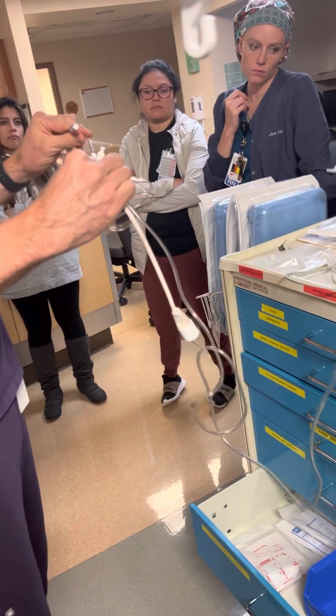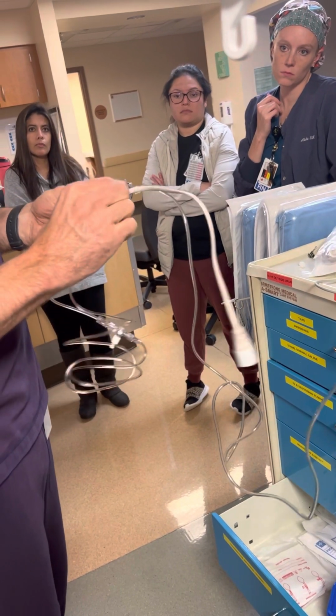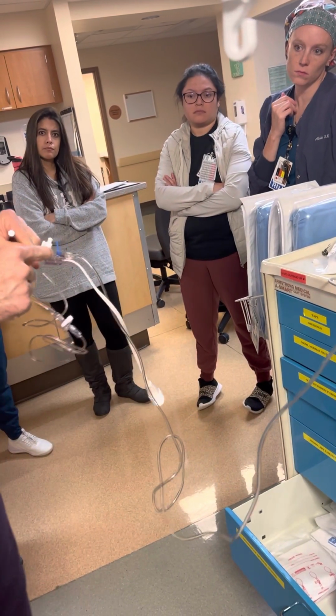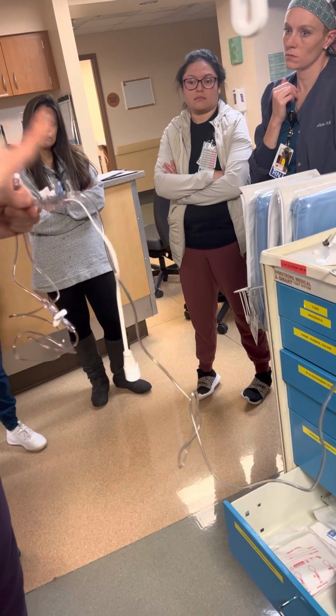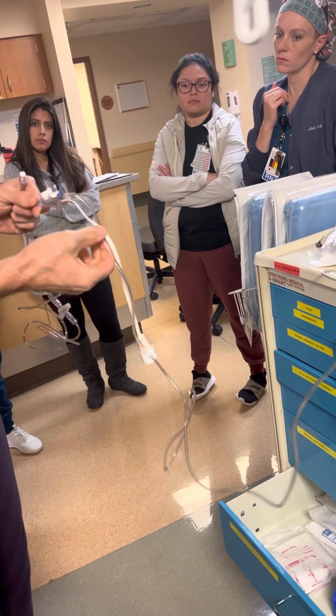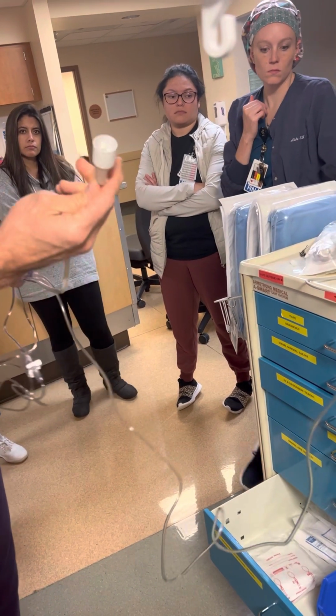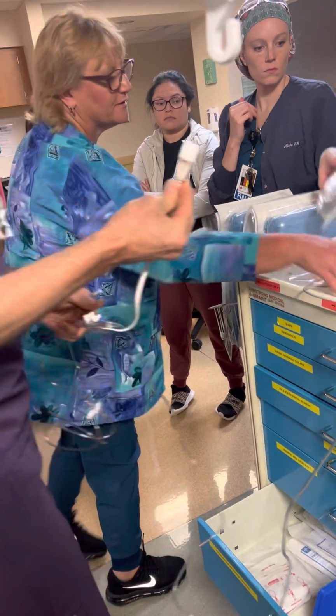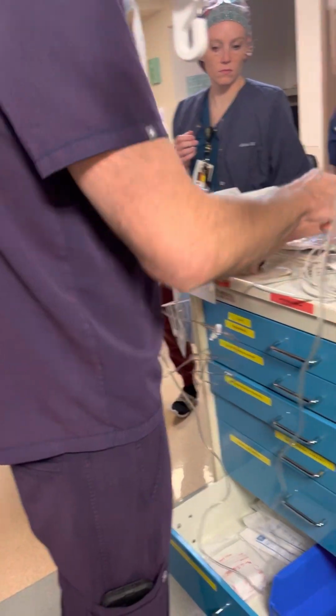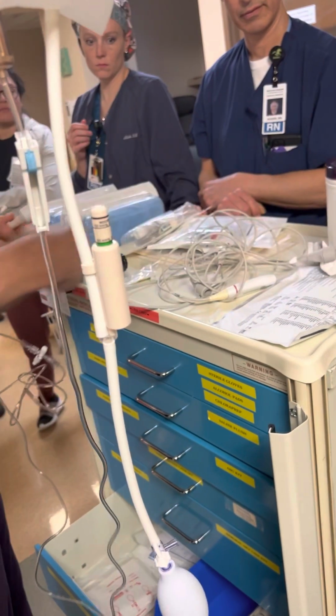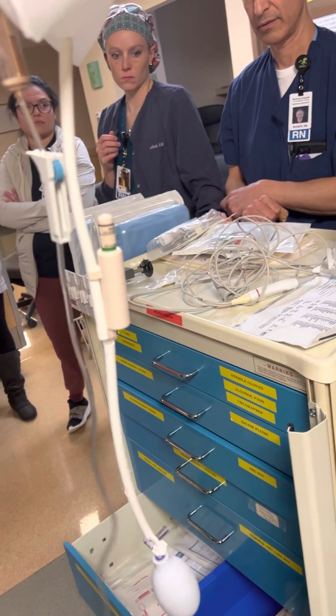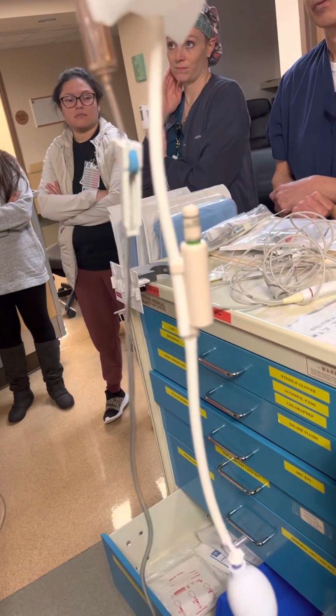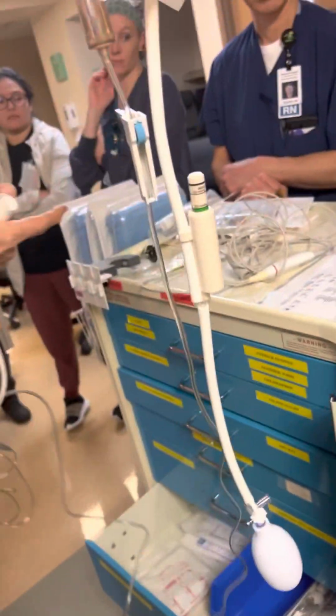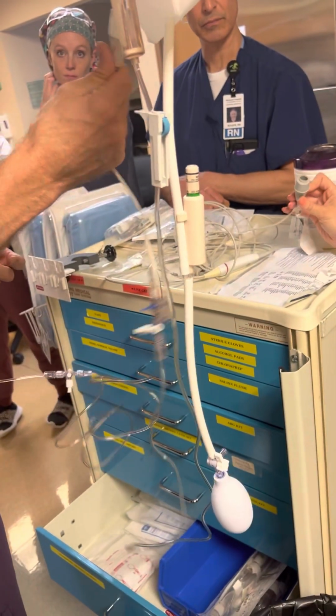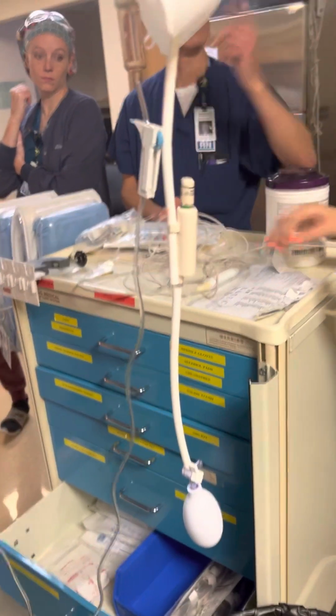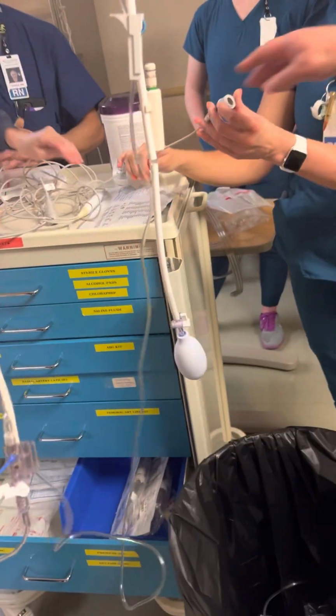Then we have to hook up this transducer. This is going to be what measures the pressure. It's relative pressure. It has this handy little connector that we have to hook up to the machines. Some of the machines should automatically populate a pressure. So do you want to plug this in? I do. See if we can get this to read a pressure.